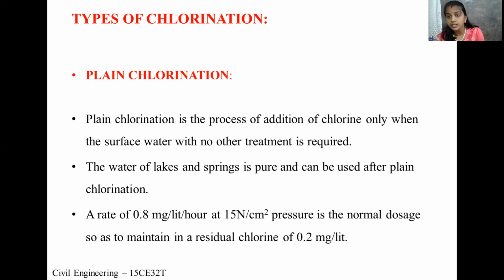At what pressure it needs to be applied? 15 Newton per centimeter square pressure. Then if this amount of chlorine at this pressure is applied, it could give a residual chlorine of 0.2 milligram per liter, which is required.